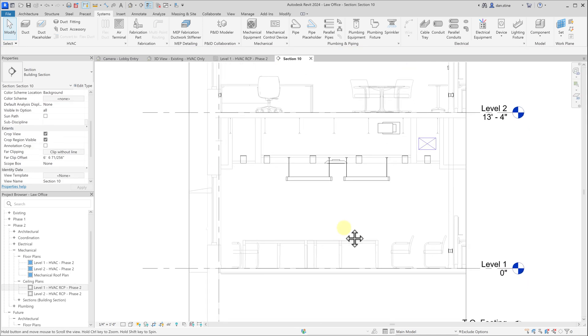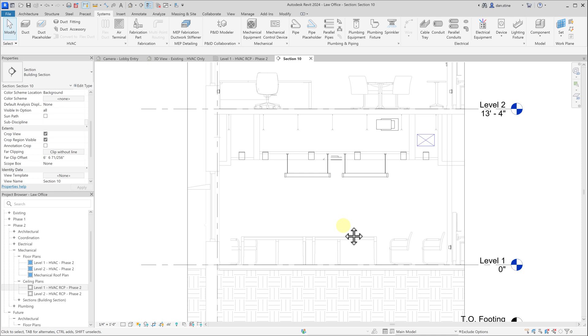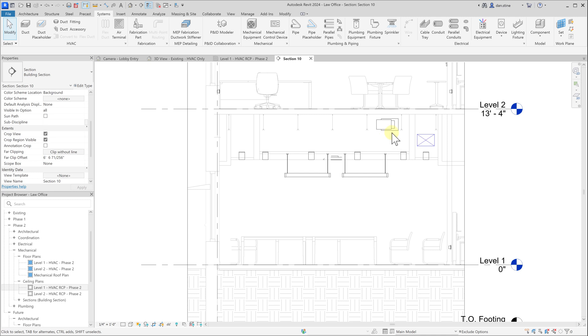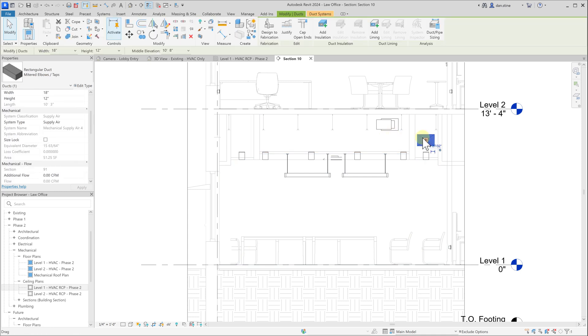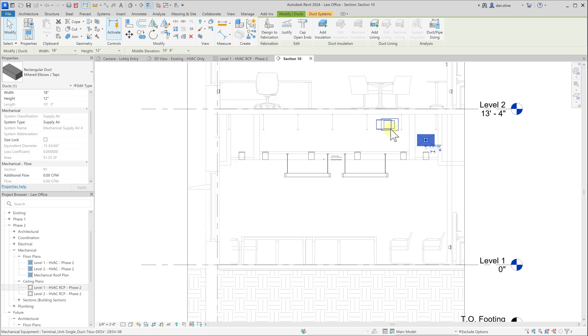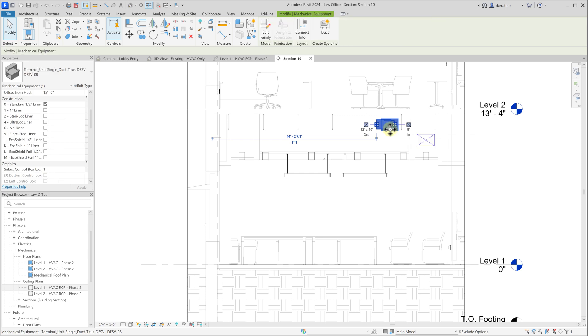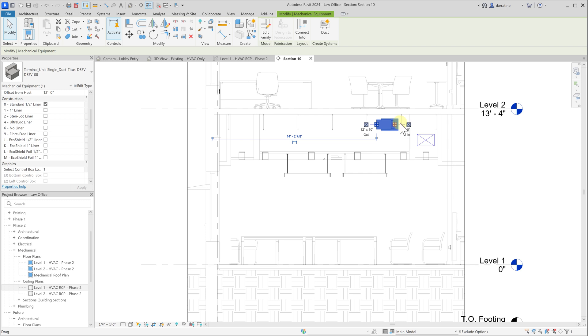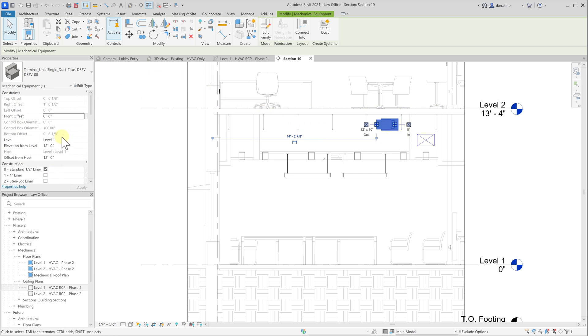In this section, we'll look at the first floor condition, and we'll see that this VAV box is quite high up into the joistwork. If we select this main duct, we'll see on the options bar that it's at 10 foot 8. It would be easier since we have plenty of room to move this down rather than trying to work the ductwork through the bar joist. So we'll select this piece of mechanical equipment and set it to 10 foot 8.